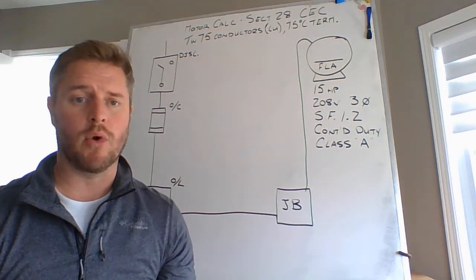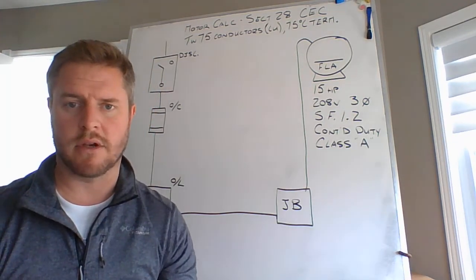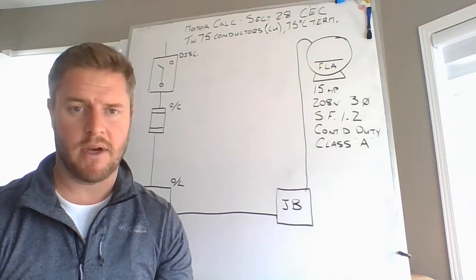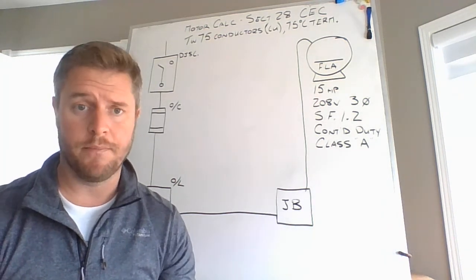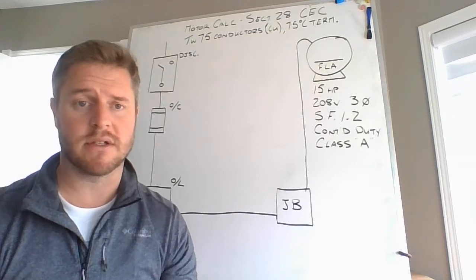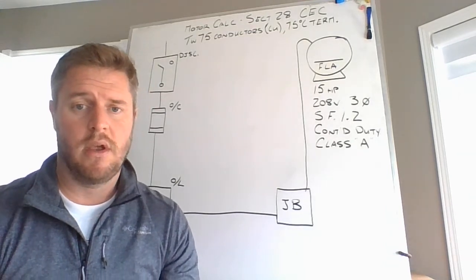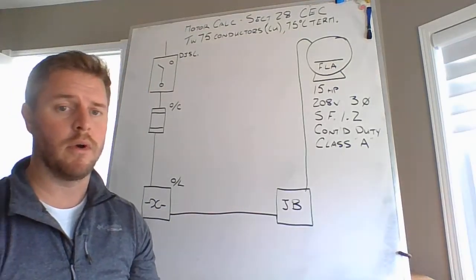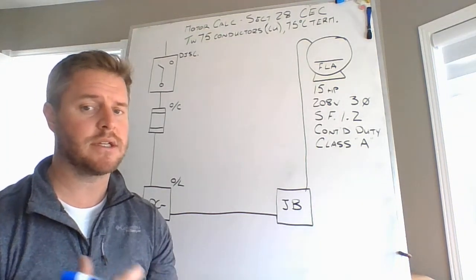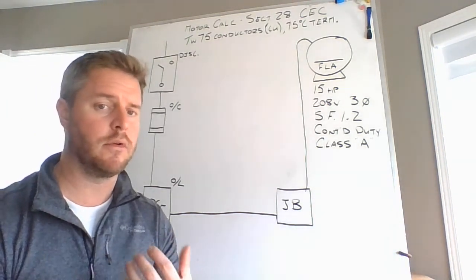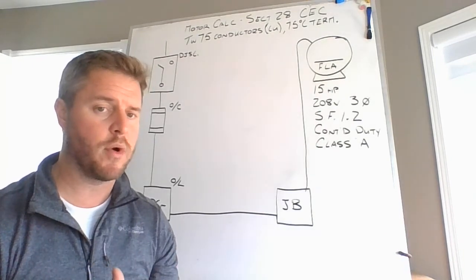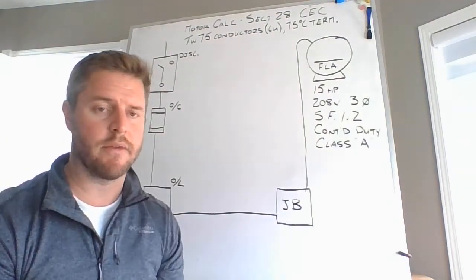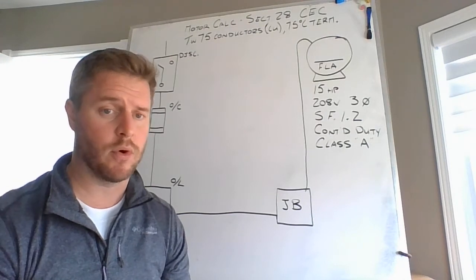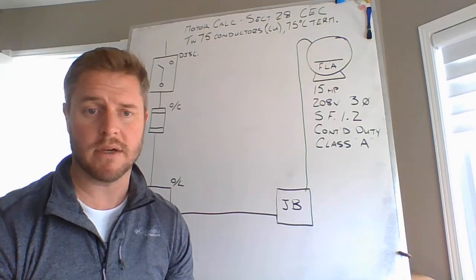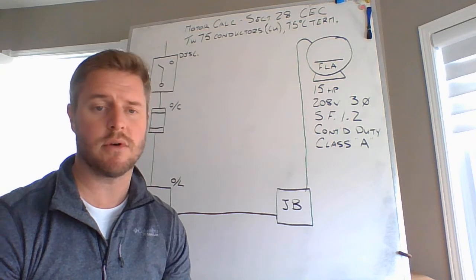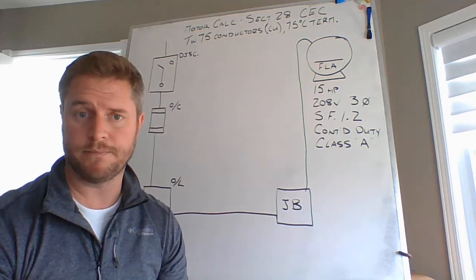So this one specific motor has some specifications to it. It's going to be fed with TW75 conductors that are constructed of copper, and we have 75 degrees Celsius termination temperatures. So we are going to look at terminating this motor, sizing disconnects, overcurrent devices, setting the overload component, and looking at the installation of these conductors to suffice this 15 horsepower 208 volt 3-phase service factor 1.2 continuous duty service class A motor.